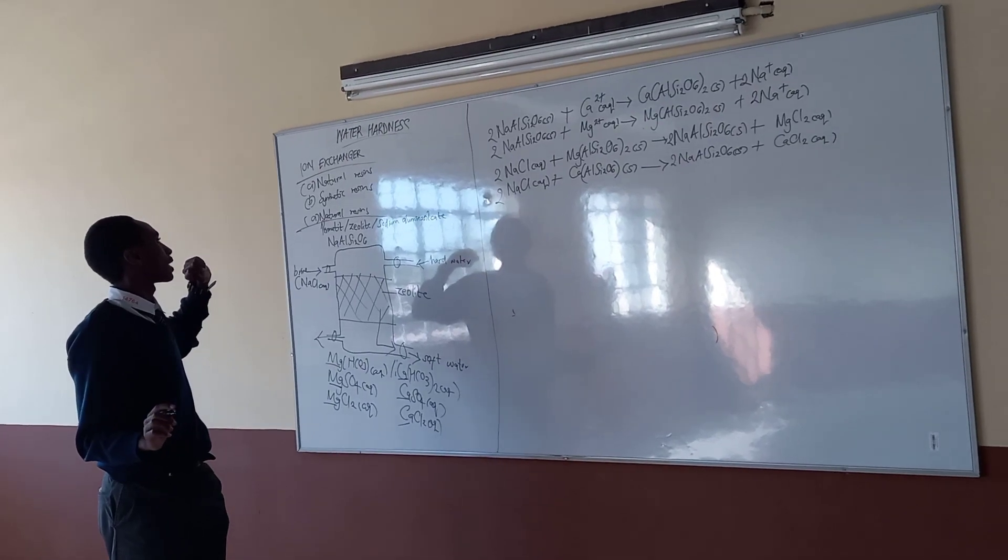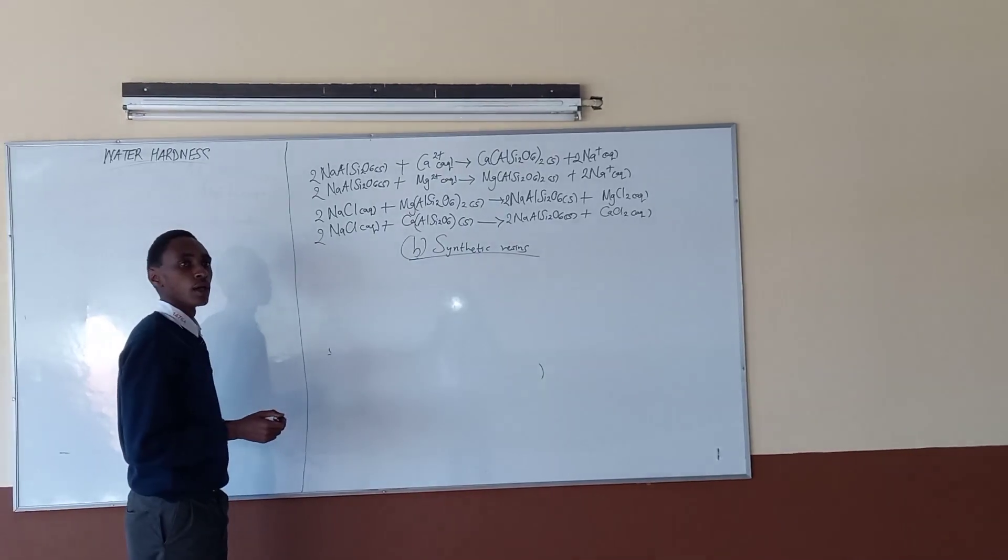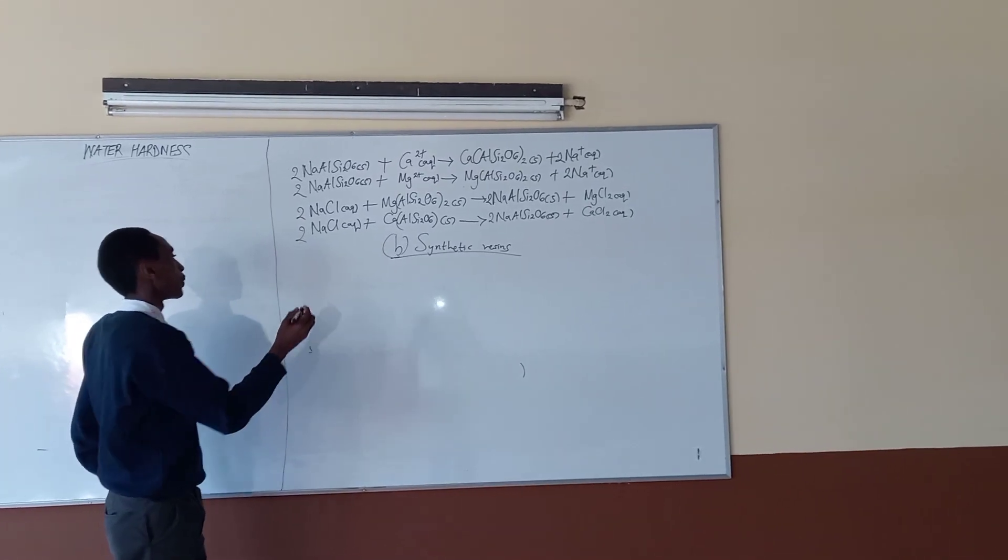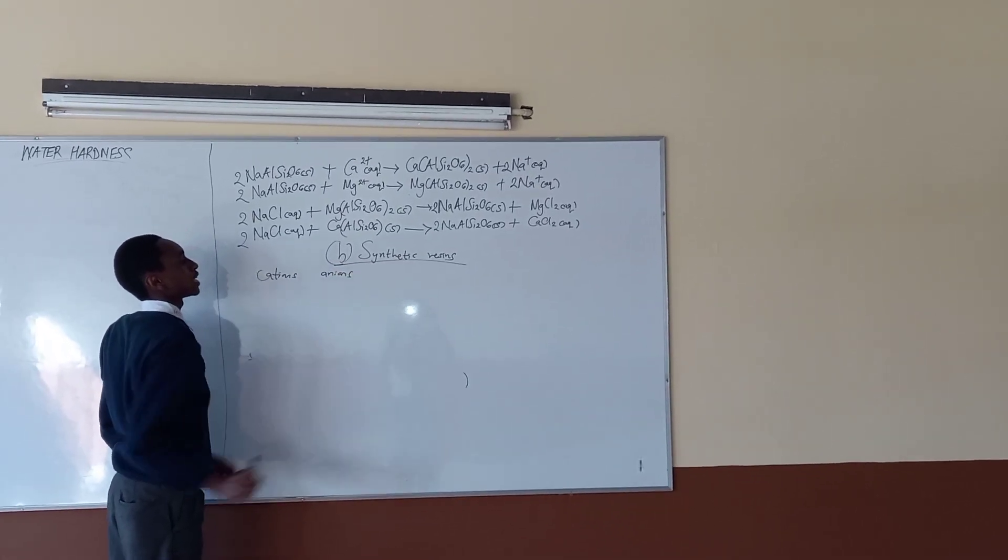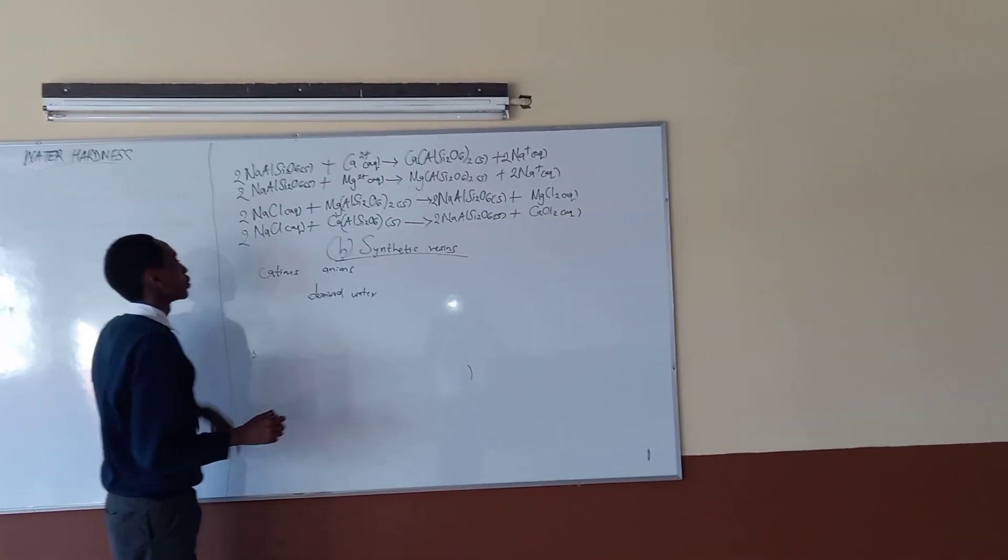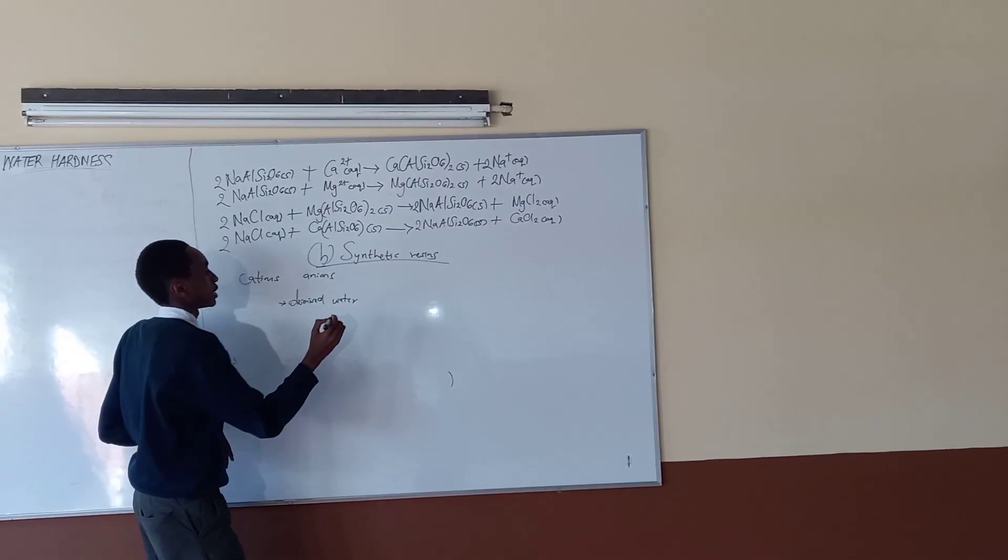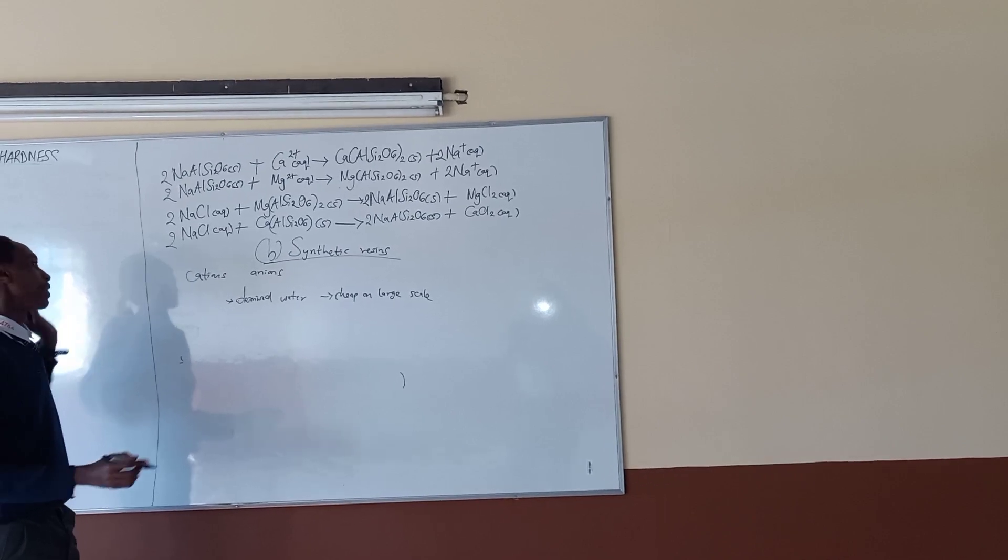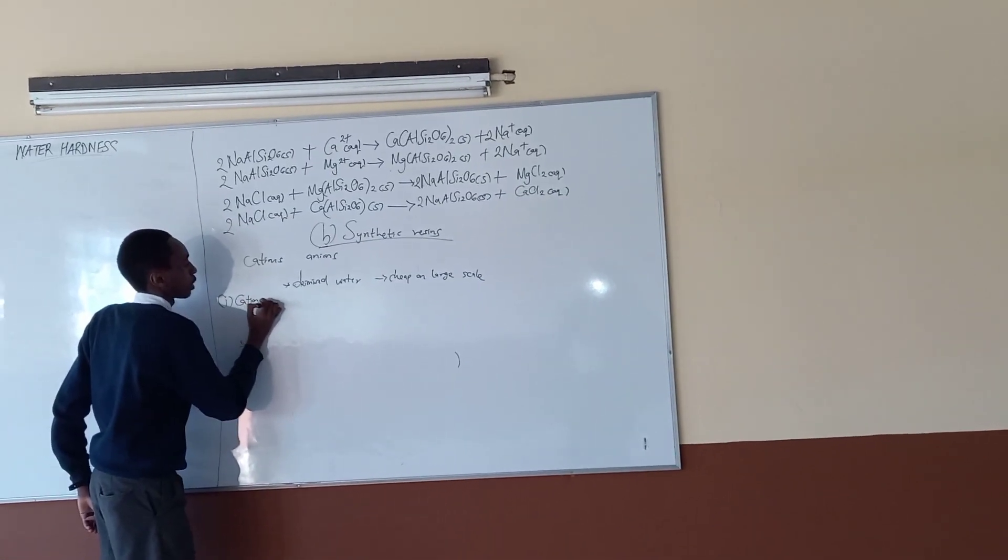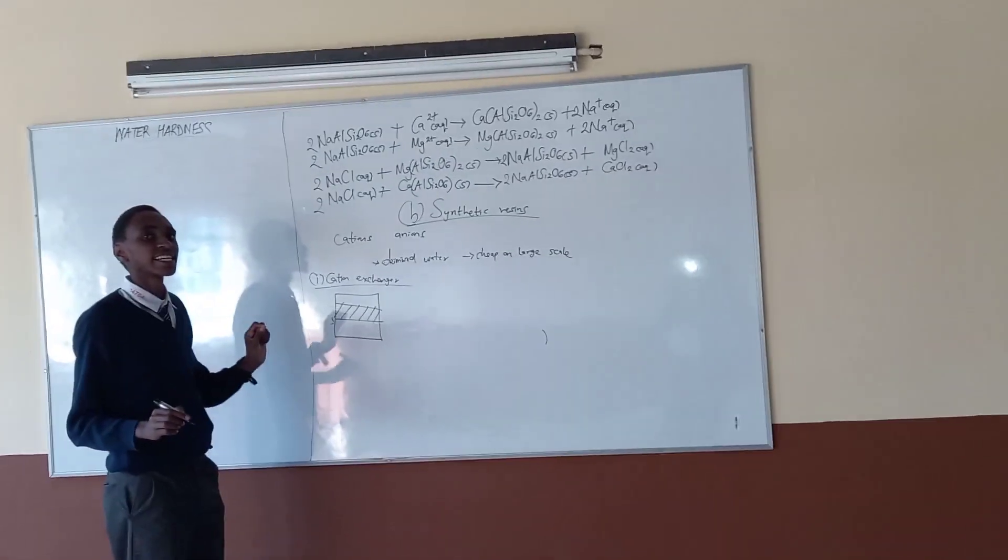So we proceed to the next step which is synthetic resins. Part B of our topic. When we use the synthetic resins, we get to remove the cations and anions. So what you get as soft water will be called deionized water. It won't have either the cations or anions. So this is an advantage. Another advantage is it's cheap and it's long-lasting. So let's break this down. The synthetic resins, there is part one, cation exchanger. This is like a tank.